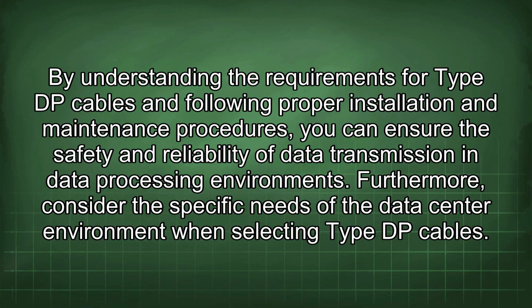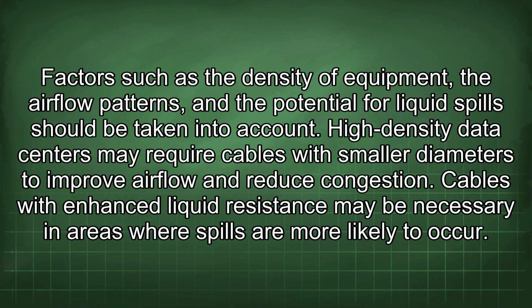Furthermore, consider the specific needs of the data center environment when selecting Type DP cables. Factors such as the density of equipment, the airflow patterns, and the potential for liquid spill should be taken into account. High-density data centers may require cables with smaller diameters to improve airflow and reduce congestion. Cables with enhanced liquid resistance may be necessary in areas where spills are more likely to occur.